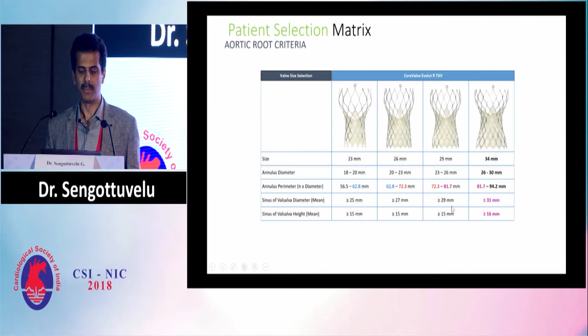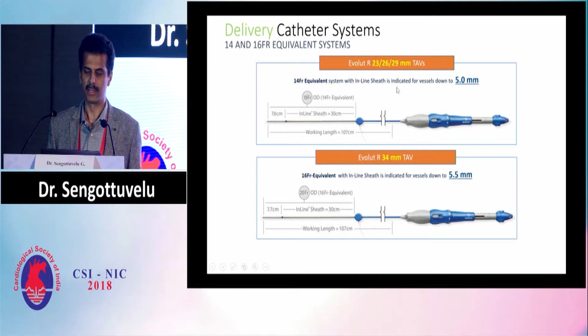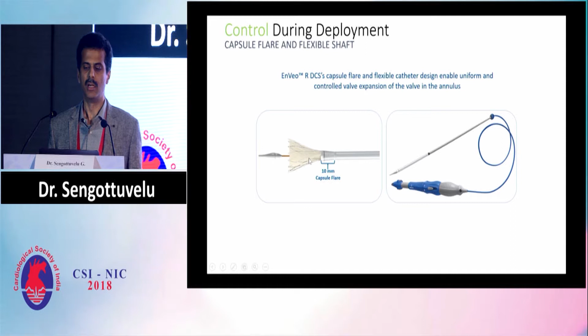The delivery systems, as I told you, are one of the lowest profile delivery systems available in the market today. This is a 14 French inline sheath, which again is the lowest profile. And for a 34 millimeter, you have a 16 French inline sheath. And if we have a big access site, we can also have the option of putting in a sheath. We need an 18 French for the smaller size, and for the 34 millimeter, we need a 20 French sheath. So the capsular flare is again one of the important features of the Evolut R valve. It enables a uniform and controlled valve expansion into the annulus.